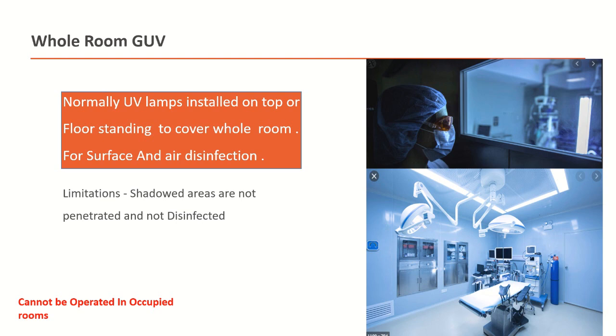The penetration level is very less. This cannot be operated in occupied rooms, and this unit should be handled by qualified and trained staff. And secondly, in these cases, you should provide safety mechanisms such as sensors which can detect human presence and immediately turn off the system.